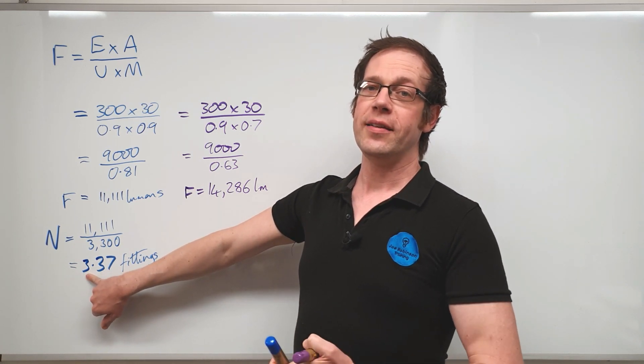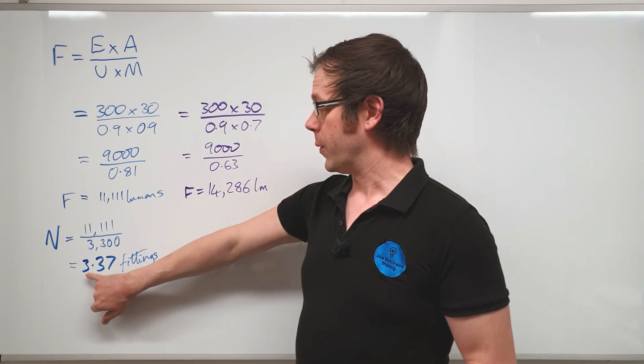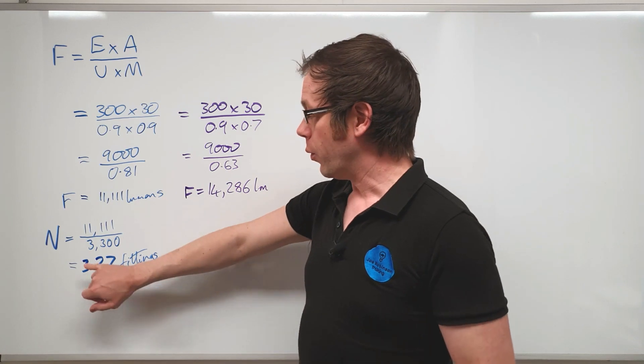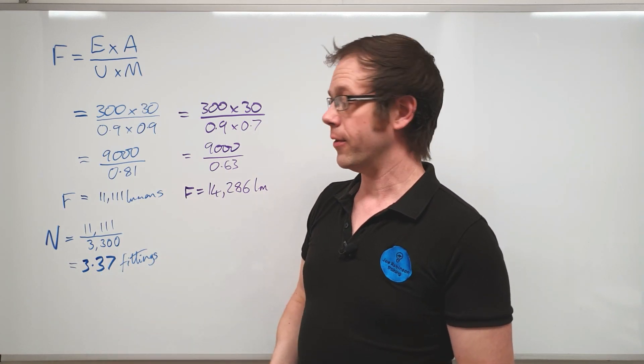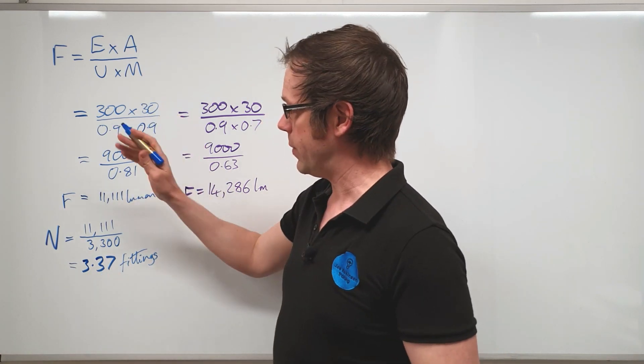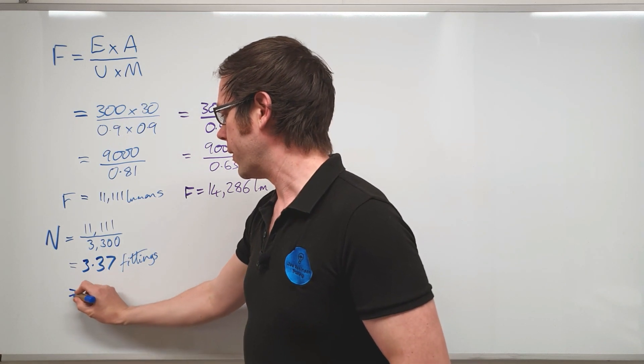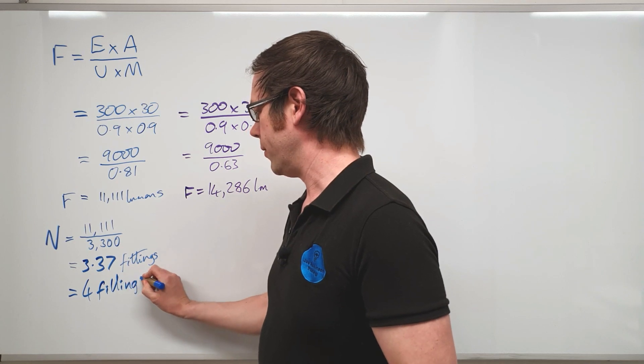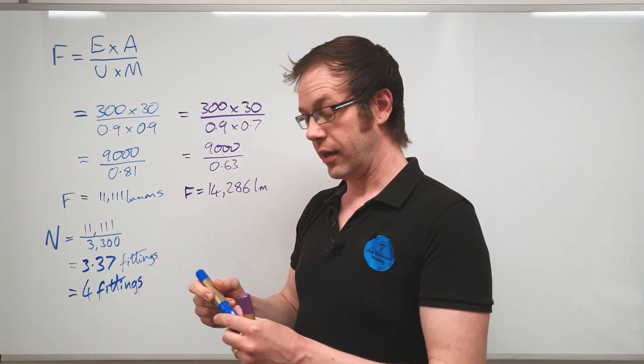But obviously if we only select three fittings for this space we're not going to have enough luminous flux for that area. So we always have to round this up to the next value. So that means that for this particular requirement we're going to need four of those Collingwood fittings installed into that space in order to achieve the correct illuminance level.